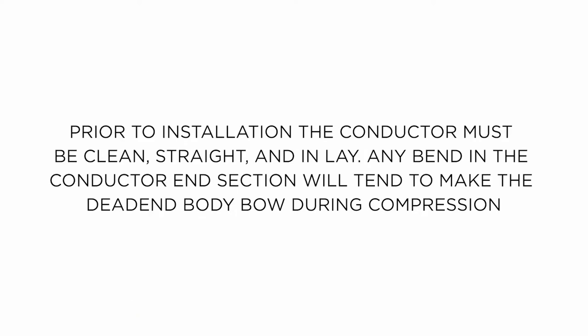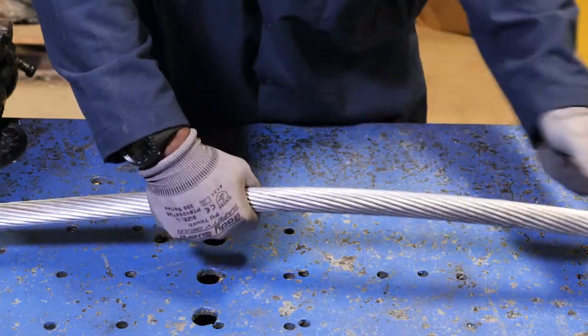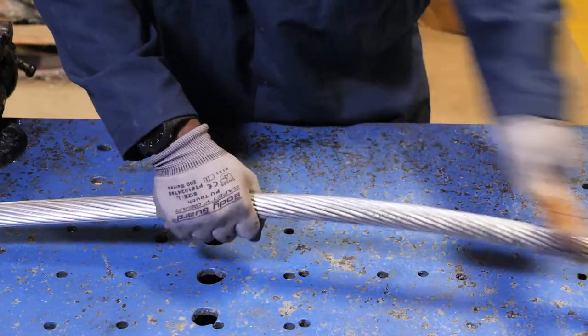Prior to installation the conductor must be clean, straight, and in lay. Any bend in the conductor end section will tend to make the dead-end body bow during compression. Wire brush the conductor after straightening to remove any oxide layers on the conductor.